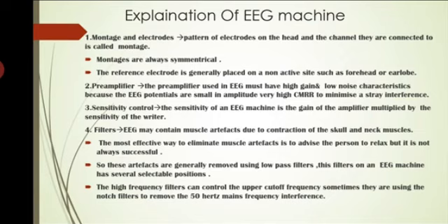The filters on the EEG machine have several selectable positions. The high-frequency filters can control the upper cutoff frequency. Sometimes notch filters are used to remove the 50 Hz frequency from mains.